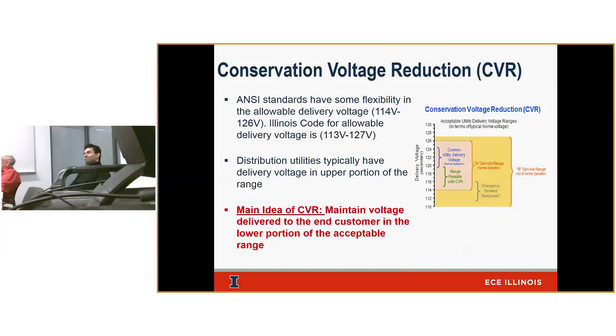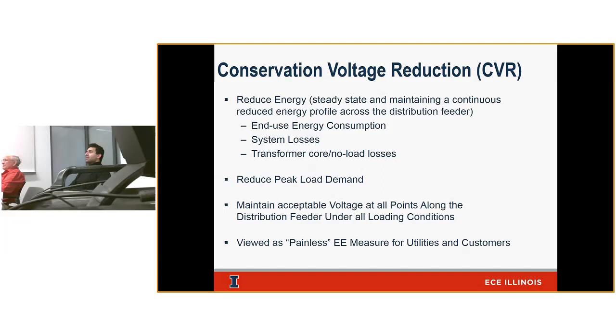Back to CVR: the main idea is to maintain voltage delivered to the end customer in the lower portion of the acceptable range. Why CVR? We're trying to reduce energy through steady state and continuous reduced voltage. It also helps system losses overall — we'll talk more about the VAR component. Transformer core no-load losses also get reduced when you reduce voltage. During peak load demand, reducing the voltage can reduce that peak demand and reduce stress on equipment and infrastructure.